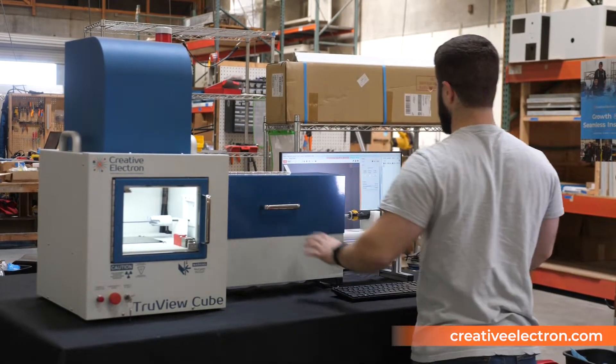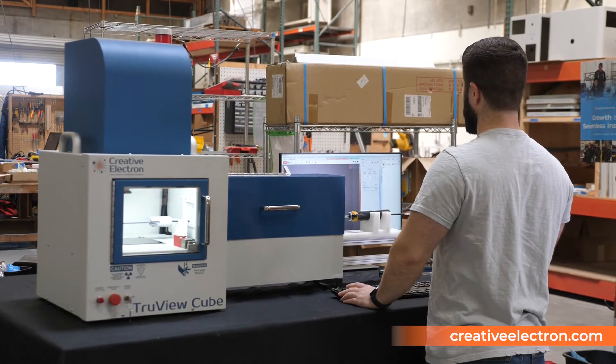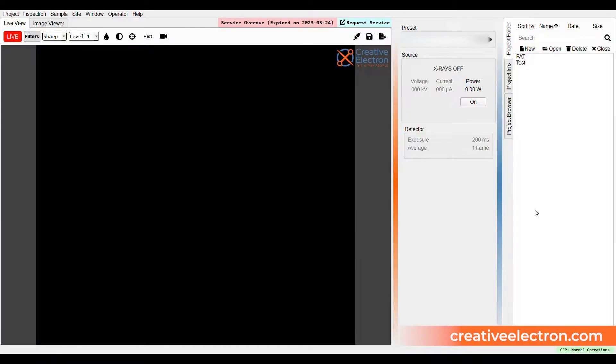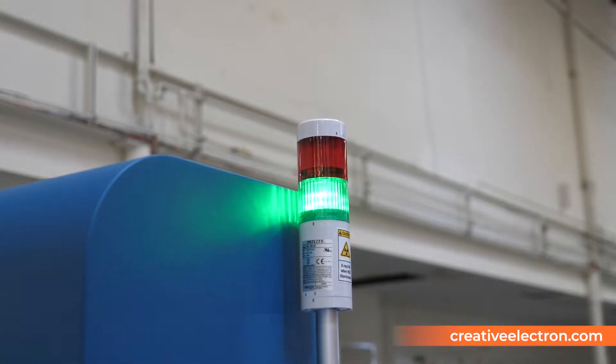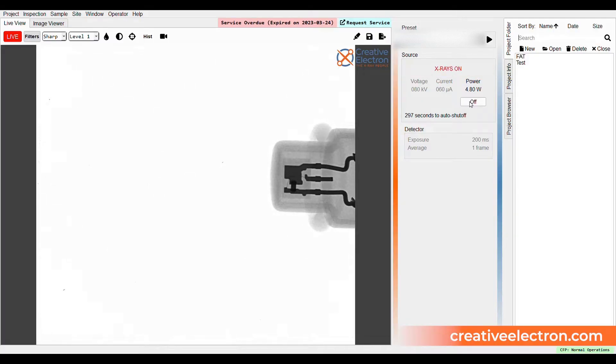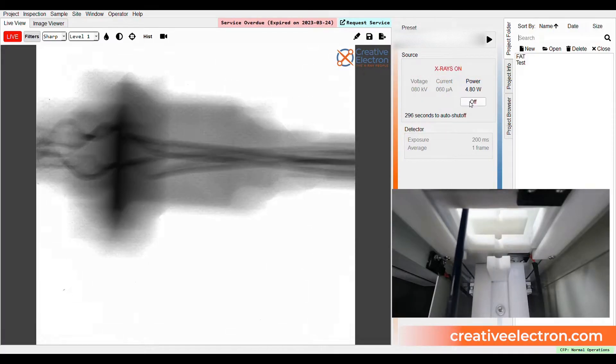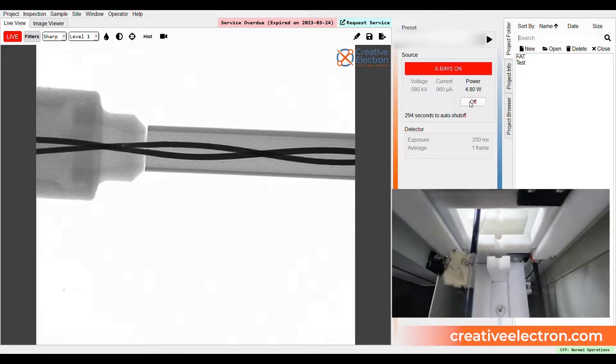To load a catheter into the system, you start by lifting the side carriage box cover. This gives access to insert the catheter into the system through a shutter opening and insert the handle into a sliding handle fixture.